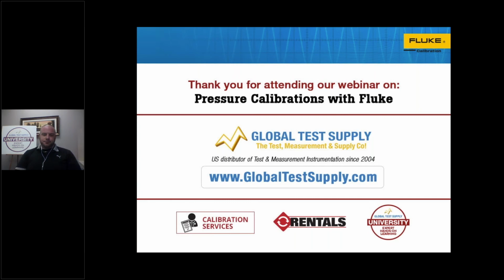Calibration intervals have a lot to do with the risk that you're willing to take. Manufacturers typically will specify a 1-year recalibration cycle. There are some statistical numbers behind what decisions you make. If you have critical processes, you may be more interested in a 6-month calibration. Less critical might be a 2-year calibration.